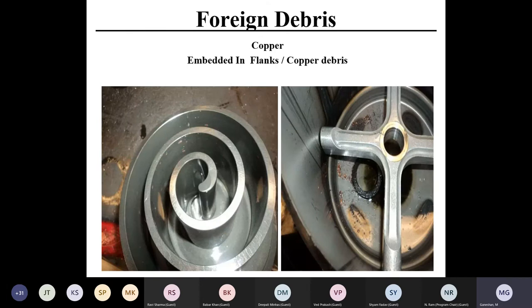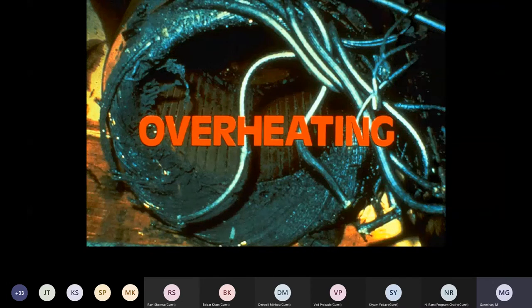Foreign debris, I was telling about, the clearances are less than one micron. Even one small piece of debris is enough to spoil our compressors. Another major problem is overheating. The compressor's capacity is limited; suction can run from 75 psi for R22, or maybe 35 psi for R134, up to maybe 120, or whatever the design is. A compressor can overload for two reasons: one is low suction, the other is high discharge. If both happen together, nobody can save it. So lower suction than design and higher discharge than design can lead to overheating.